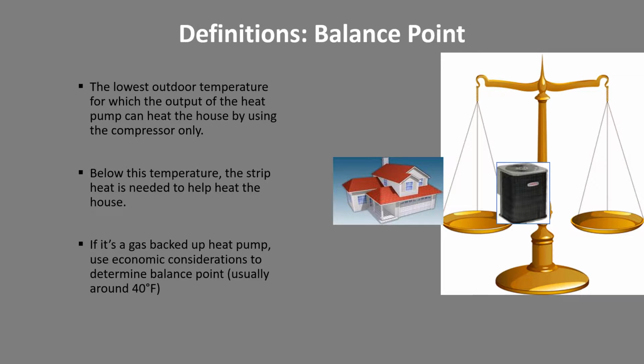Definitions, let's just talk about balance point here a little more. It's the lowest outdoor temperature for which the output of the heat pump can heat the house by using the compressor only. Below this temperature, the strip heat might be needed to come on.